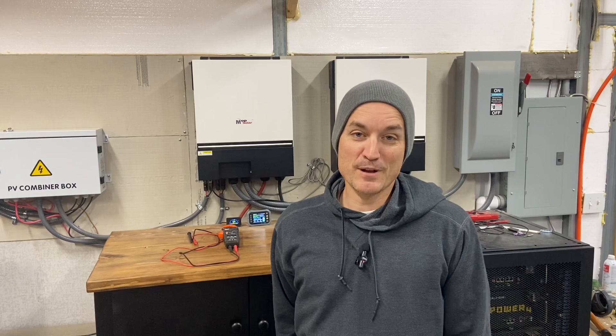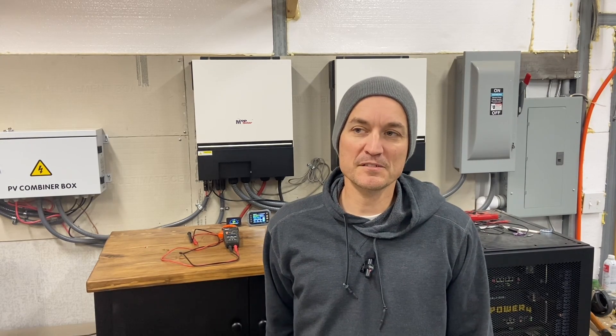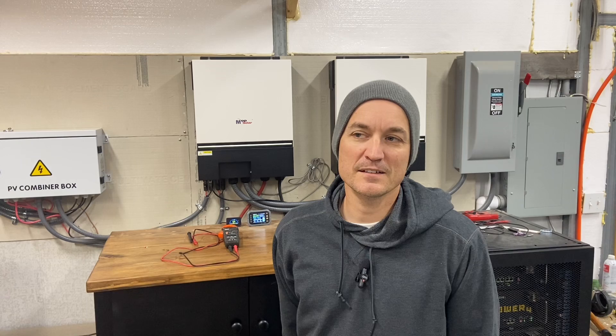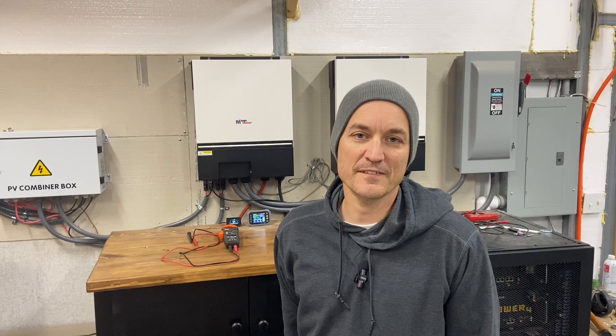So to wrap up - I really like the units so far. They have decreased my starting amps, looks like five or six amps on one unit. The other unit hasn't started up enough times to measure yet. I'll patch in a screenshot of the app. I had some wiring questions and was able to send a diagnostic report to Microair to verify everything was correct - I really like that Bluetooth feature for troubleshooting and customer support.